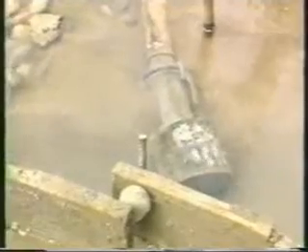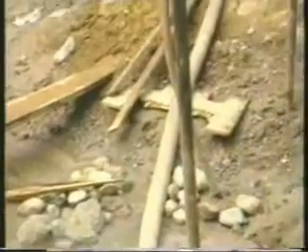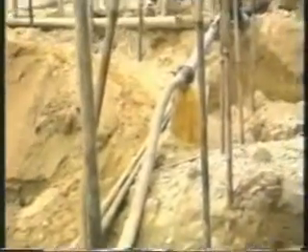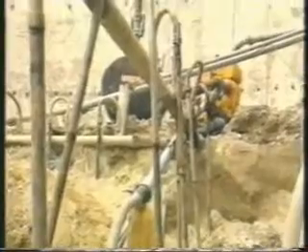Direct suction can be performed with any type of self-priming or submerged pump, and consists in pumping the water from the excavation directly through the suction pipe and a grating at the bottom. It is used specifically for lowering and emptying operations of medium size and duration in fairly compact, silty, clayey soils with low permeability, or for stable gravelly soil with high permeability, in which case high delivery pumps must be used.